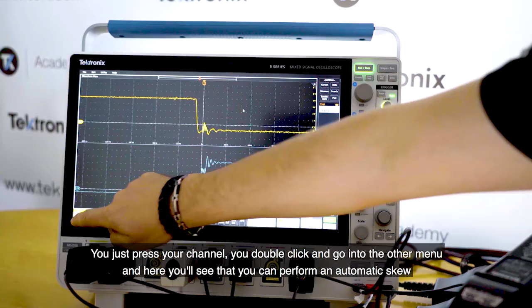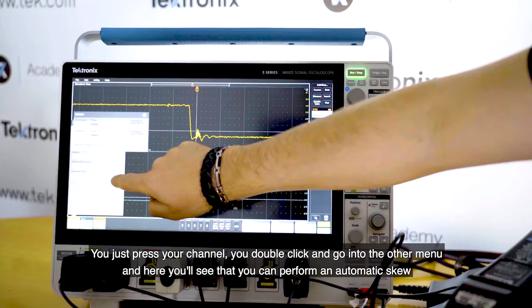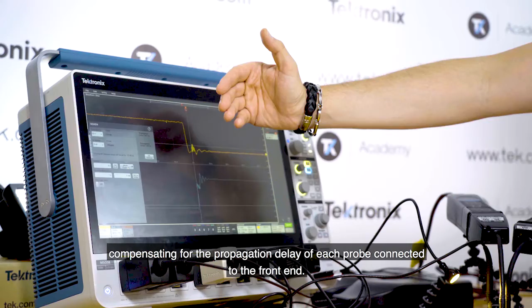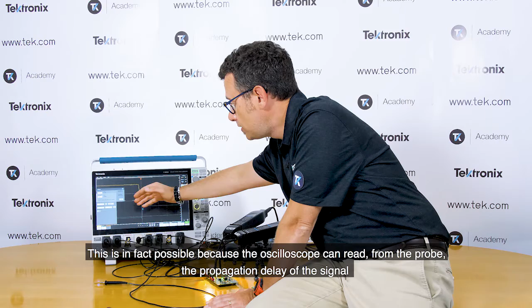And with Tektronix, you can do that automatically because this is quite an easy procedure. You just press your channel, double click and go into the other menu, and here you see that you can perform an automatic skew, compensating for the propagation delay of each probe connected to the front end. This is possible because the oscilloscope can read the propagation delay of the signal from the probe and make sure it compensates for it.